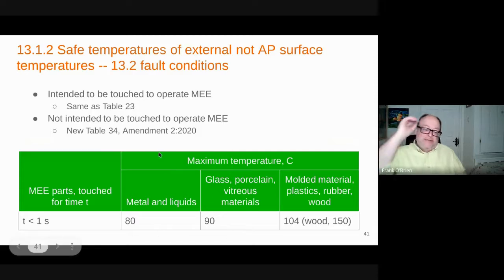So in some ways, Amendment 2 restricts that interpretation sheet. But maybe that interpretation sheet wouldn't be as relevant for as many situations. So then Amendment 2 is friendlier. In any case, this was needed, and we got it into the Amendment 2. And so we do allow surface temperatures to be hotter than we'd normally like, but it's because we're in a single fault condition. And hopefully that's somewhat detectable.